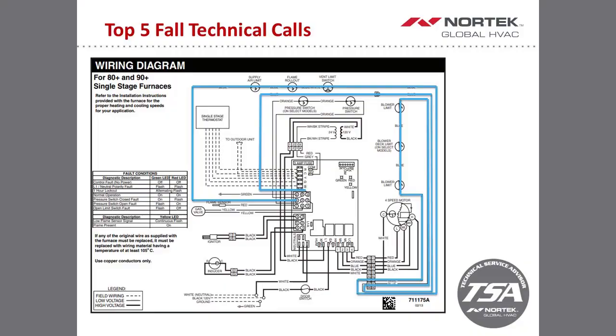What we have here is a wiring diagram of a single stage furnace. This will apply to the high efficiency 90 plus stuff, your 92 and 95% single stage furnace, along with the 80% standard furnace. So you'll see you have 2 blue wires coming out of the 9-pin plug, and this will go through the entire limit circuit. And then it snakes down to your blower compartment where you'll have 2 blower limits, and then comes back to the 9-pin plug. So again, the limit circuit in the furnaces is going to be your blue wire circuit.